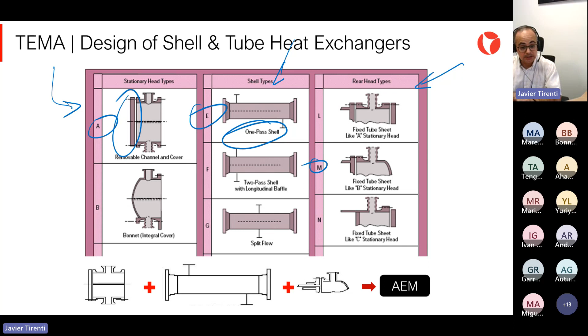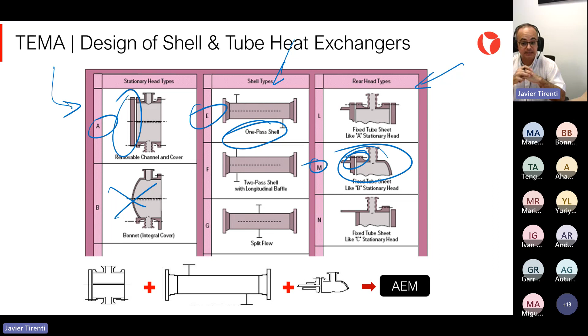A shell and tube heat exchanger that is AEM is going to have only one pass on the shell. It is going to have one blind cover on the stationary head for maintenance, something that we cannot find in the B category, for example. And it's going to have a rear head type that is able to attach directly to the shell. I am just mentioning two or three things for us to understand that every selection has a connotation, and we are going to have some characteristics derived from that selection.